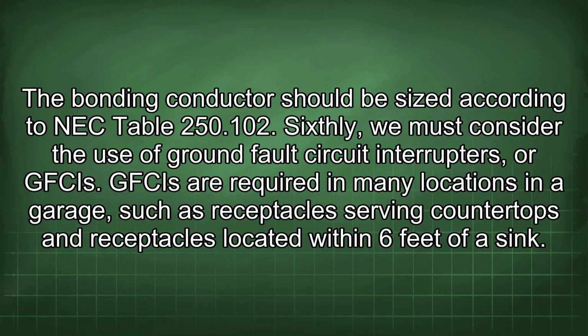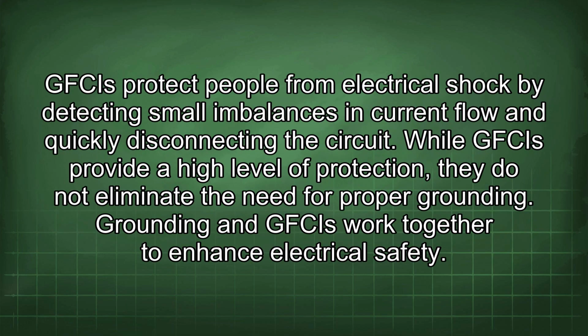Sixthly, we must consider the use of ground fault circuit interrupters, or GFCIs. GFCIs are required in many locations in a garage, such as receptacles serving countertops and receptacles located within 6 feet of a sink. GFCIs protect people from electrical shock by detecting small imbalances in current flow and quickly disconnecting the circuit.